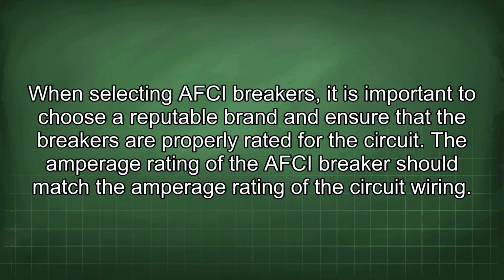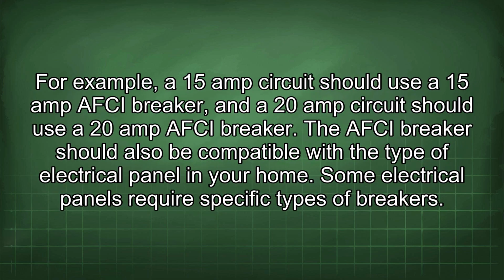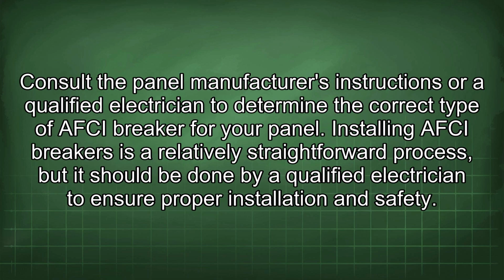When selecting AFCI breakers, it is important to choose a reputable brand and ensure that the breakers are properly rated for the circuit. The amperage rating of the AFCI breaker should match the amperage rating of the circuit wiring. For example, a 15 amp circuit should use a 15 amp AFCI breaker, and a 20 amp circuit should use a 20 amp AFCI breaker. The AFCI breaker should also be compatible with the type of electrical panel in your home. Some electrical panels require specific types of breakers. Consult the panel manufacturer's instructions or a qualified electrician to determine the correct type of AFCI breaker for your panel.